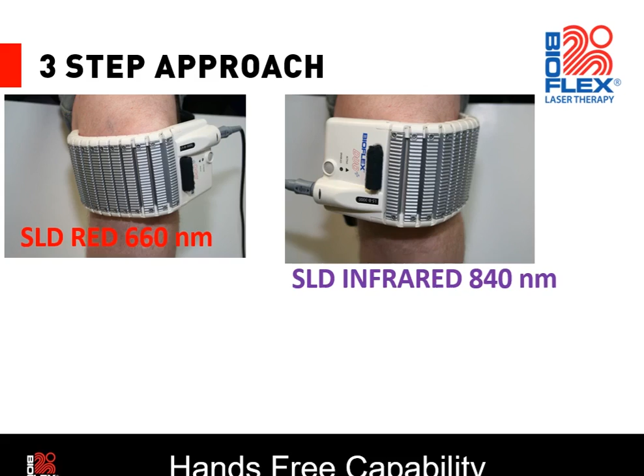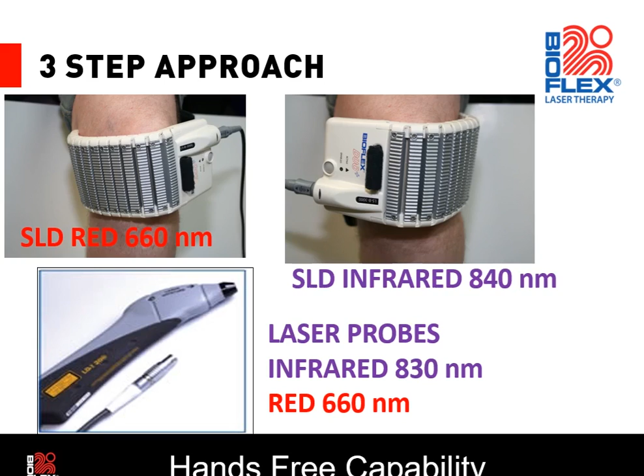And after this, we then move on to a much higher intensity light with respect to using a laser probe. We have an infrared at 830 nanometers at 200 milliwatts, and a red laser probe at 660 nanometers at approximately 100 milliwatts. So the idea here is to initially treat the superficial tissues and the blood with the red and infrared arrays, followed by a much deeper penetration with respect to an active penetration of using laser probes of both infrared and red. And I'll explain a lot more about this as we move on with the training webinars.